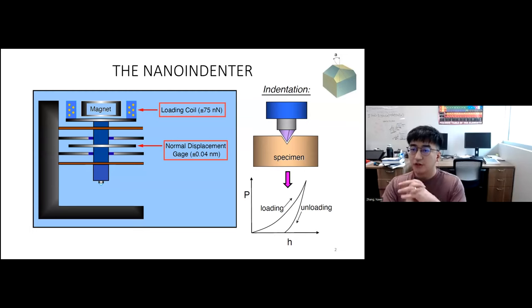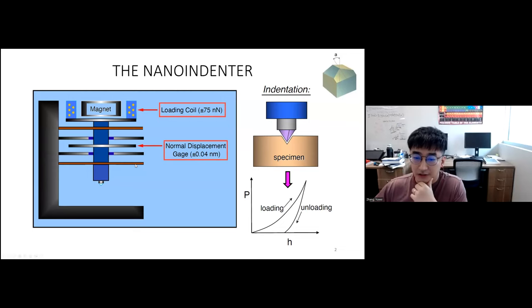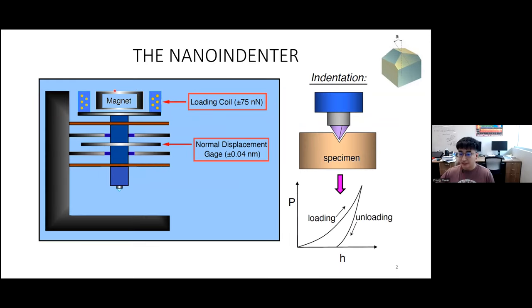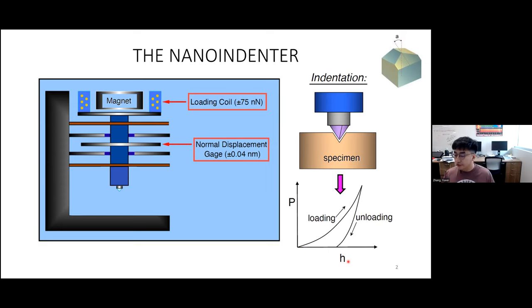For the audience who are not very familiar with nanoindentation, it's basically a load cell. The load is added by the magnetic coil and transforms through a rigid column, and the displacement is measured by a displacement gauge. At the end of this rigid column is a pyramid diamond indenter which will penetrate through a sample surface. During operation, the instrument records load and depth curves, which we can use to measure mechanical properties like modulus, hardness, and fracture toughness.